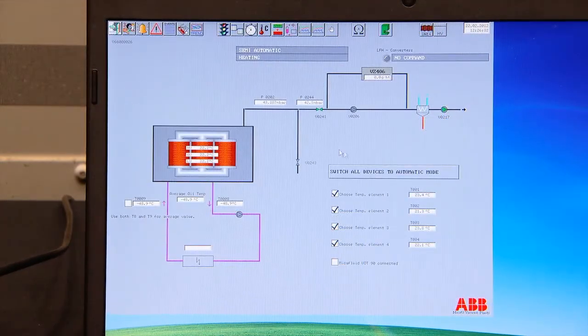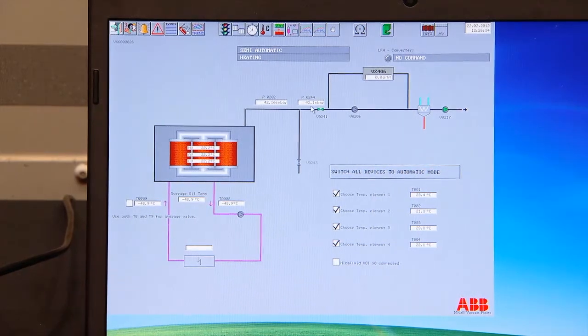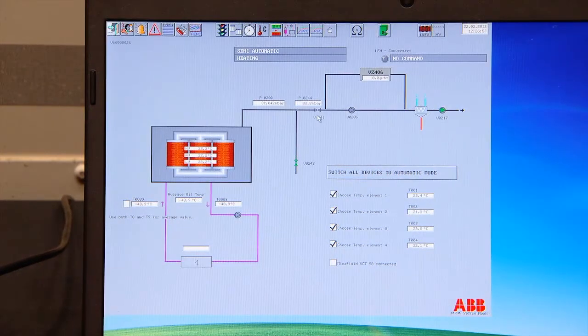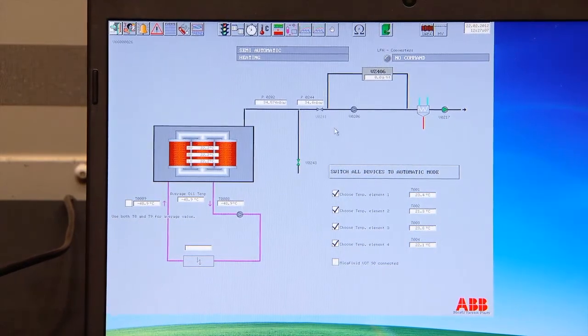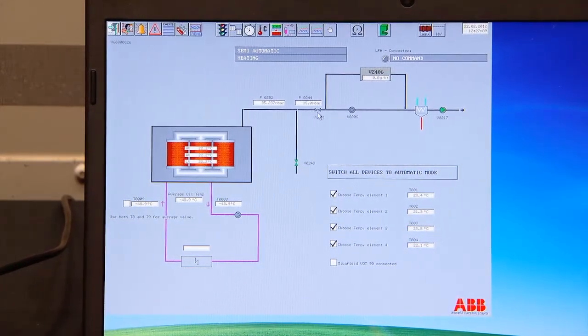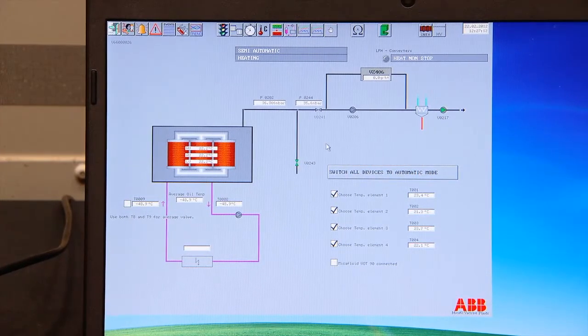What we can see here now is that we are regulating the pressure around 40 millibar, as the value we put in there before. So above 40 millibar he's opening the vacuum valve. Below 35 millibar he will open the aeration valve to get it around there. This vacuum valve is a positioning valve, so he's not fully closing or fully opening. He will adjust it to whatever position is suitable to catch up for the leakage and so on. That's why the alarm is going up, because now it's automatic control, yes. Don't worry about it.